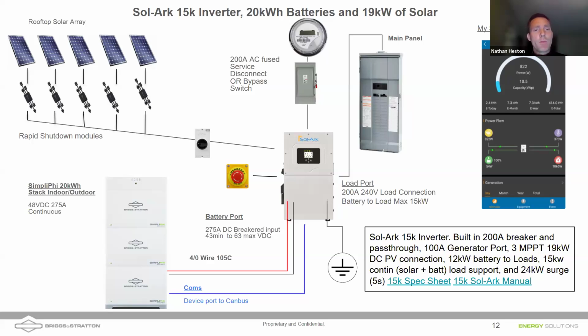Those are rapid shutdown modules. So after 2019 on your roof, if you did a roof mount array, you need essentially little relays that will turn the panels on and off at the panel level, meaning at the panel location. So not only does the string have to shut down, but the DC output of the panels has to shut down as well. So those are rapid shutdown modules. And they are kept alive by what's called a keep alive signal that comes either from the inverter if you're using an AP Smart transmitter, or from maybe Tigo, another good example, that can offer optimizers as well.